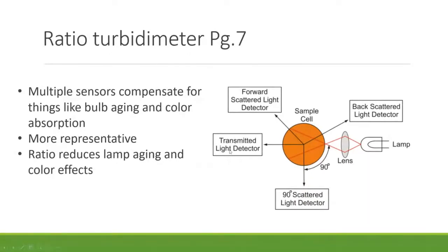The Ratio Turbidometer uses a combination of different orientations and multiple sensors to compensate for lamp aging, color absorption, and similar issues. Because it uses multiple angles, it tends to be more representative. The ratio configuration reduces lamp aging and color effects by averaging out lamp power variations, giving a more reliable measurement.